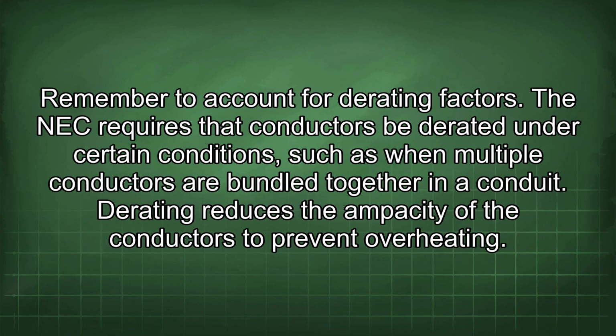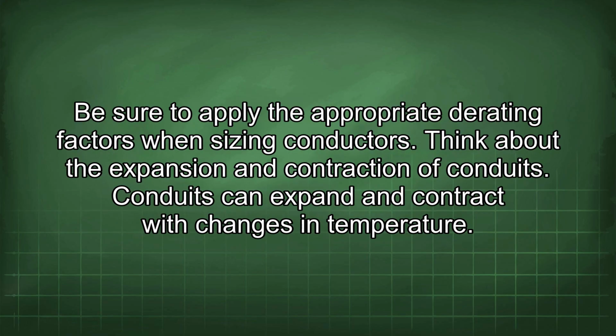Remember to account for derating factors. The NEC requires that conductors be derated under certain conditions, such as when multiple conductors are bundled together in a conduit. Derating reduces the ampacity of the conductors to prevent overheating. Be sure to apply the appropriate derating factors when sizing conductors.